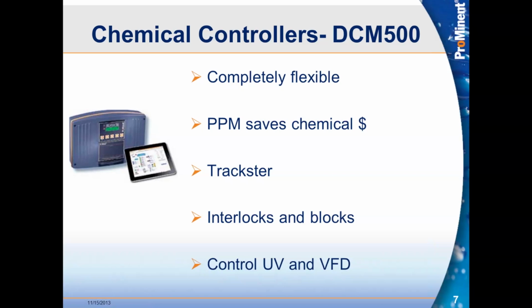Or if we have a pump pit that's below grade, we can put flood sensors into these pits, and we can alert and alarm off of that. We can text, we can email somebody, letting them know that their pump pit is in the process of flooding, and somebody better get over there pretty quick. Nobody else has this capability on their controllers. We have other facilities that are not only measuring the water temperature, but they're also measuring the air temperature in the natatorium, so that they can keep it at that optimal 2 degrees or so difference. So if somebody has a special use, if we can find a sensor for that need, chances are we can put that into the controller and do something very valuable with it. We can control other equipment, or we can at least send out alarms.